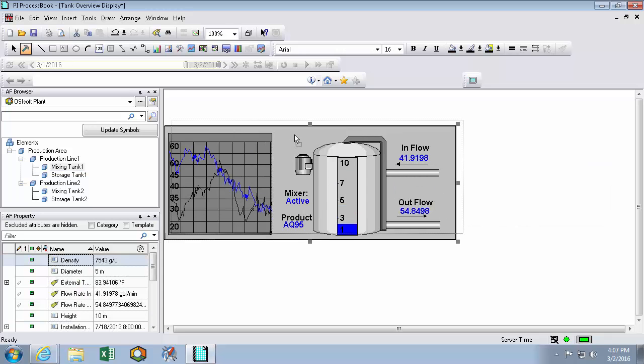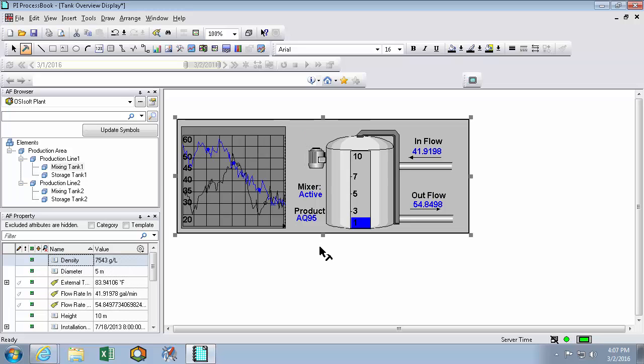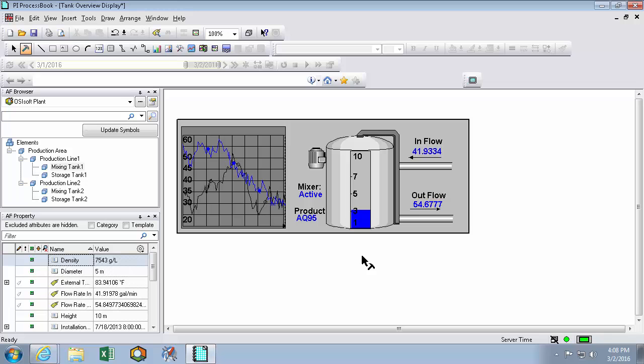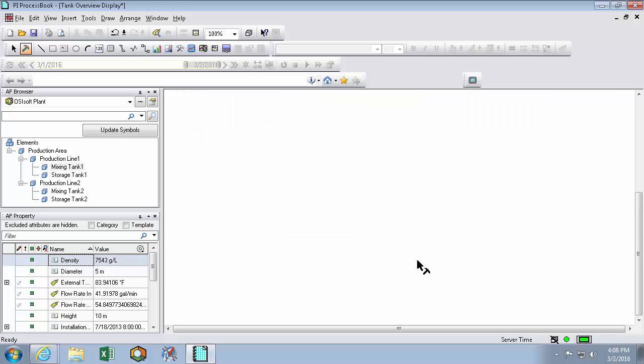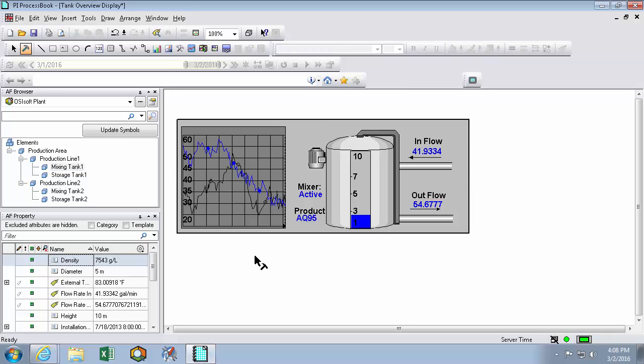So this produces the symbol that we assigned to the template. And it'll automatically assign mixing tank 1 that I dragged out onto it. Since mixing tank 1 is assigned to this symbol, we can leave this part of the display. And if we want to find anything assigned to mixing tank 1 we can right click and locate it. And the display will pan over and select the symbol that's assigned to mixing tank 1.